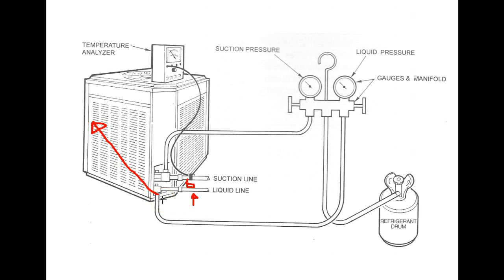Don't be looking at this and thinking that because these are so close to each other that you're measuring everything that's happening in the course of several inches. So the temperature probe is measuring the temperature of the refrigerant at this point, but your pressure gauges are measuring the pressure and temperature of the refrigerant and state of that refrigerant in the center of the condensing coil.